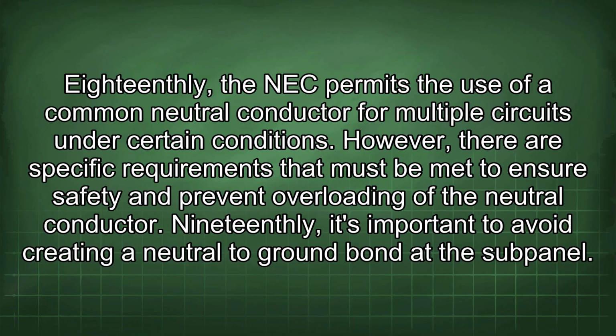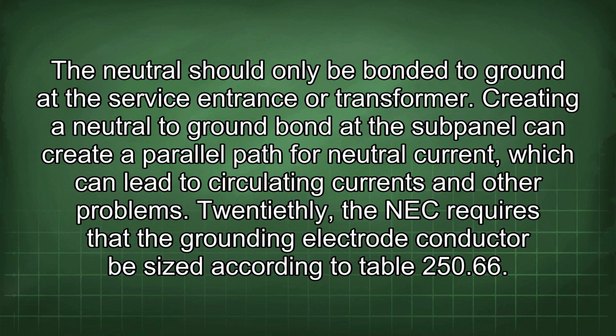18thly, the NEC permits the use of a common neutral conductor for multiple circuits under certain conditions. However, there are specific requirements that must be met to ensure safety and prevent overloading of the neutral conductor. 19thly, it's important to avoid creating a neutral to ground bond at the subpanel. The neutral should only be bonded to ground at the service entrance or transformer. Creating a neutral to ground bond at the subpanel can create a parallel path for neutral current, which can lead to circulating currents and other problems.